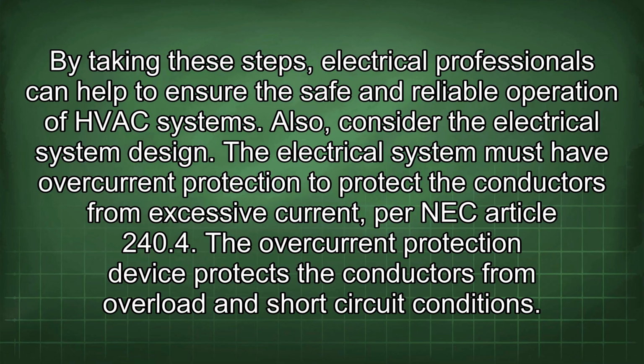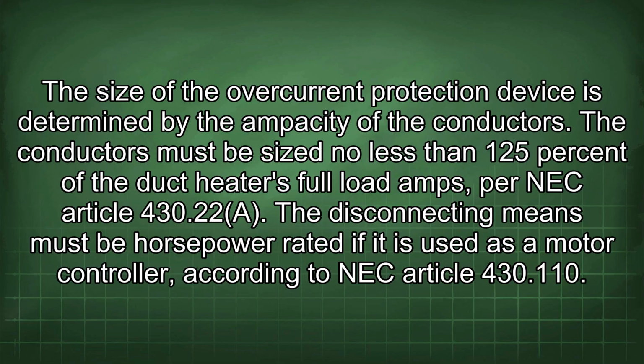Also, consider the electrical system design. The electrical system must have overcurrent protection to protect the conductors from excessive current per NEC Article 240.4. The overcurrent protection device protects the conductors from overload and short-circuit conditions. The size of the overcurrent protection device is determined by the ampacity of the conductors. The conductors must be sized no less than 125% of the duct heater's full load amps, per NEC Article 430.22(A).